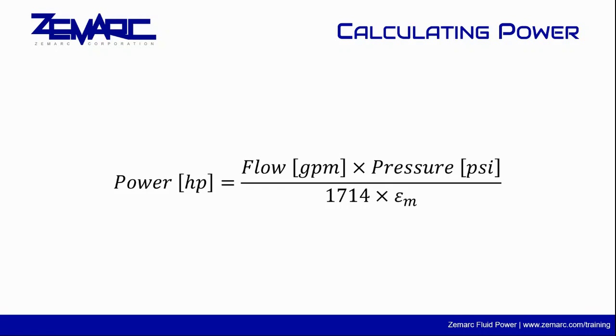Note that the efficiency of the pump means that the pump draws more mechanical power than the fluid power it outputs. The efficiency of a pump can be found in its catalog. These catalogs often have power curves that will show a more exact power rating.